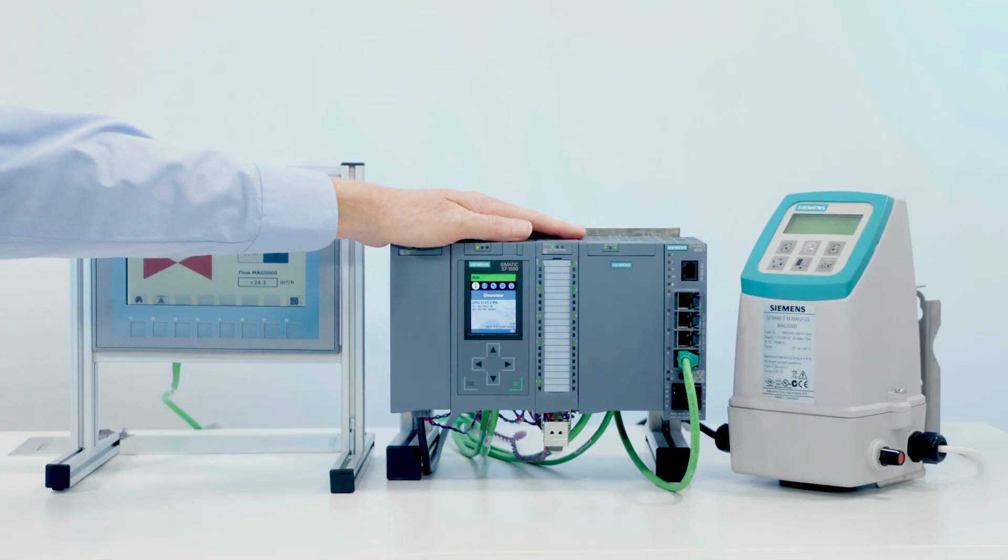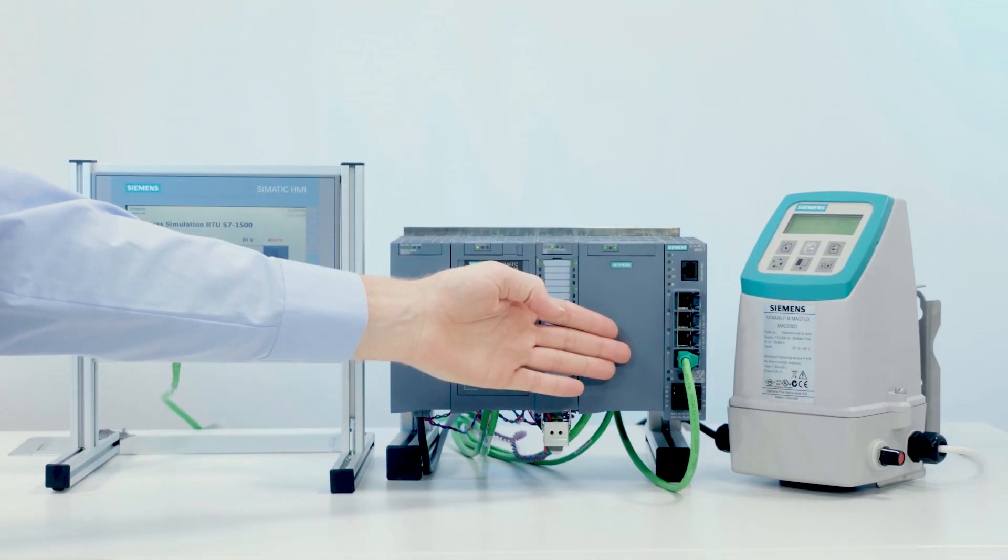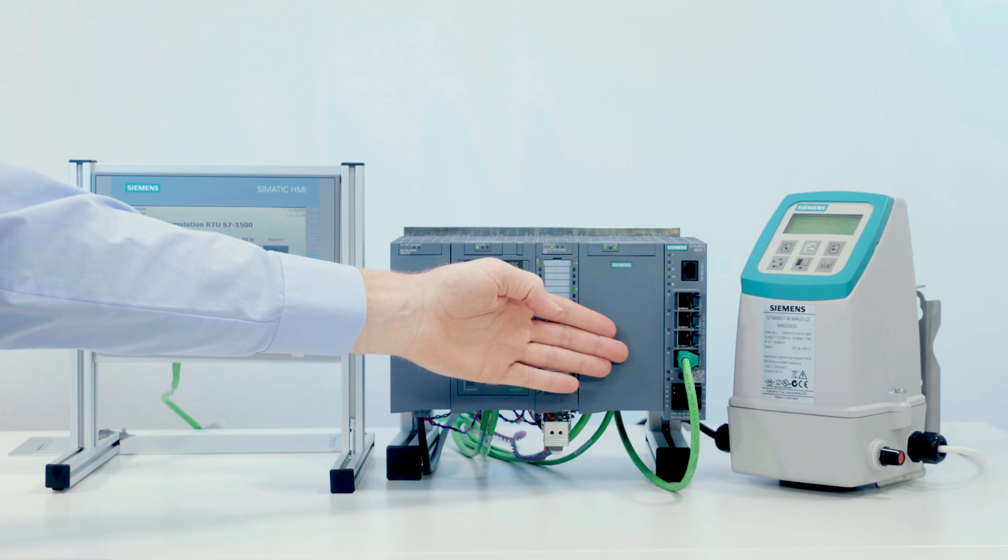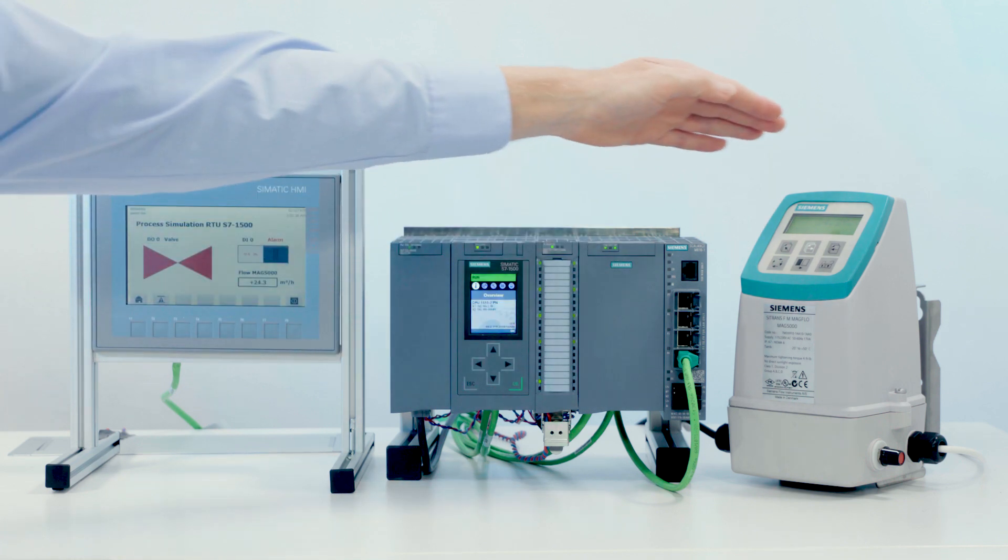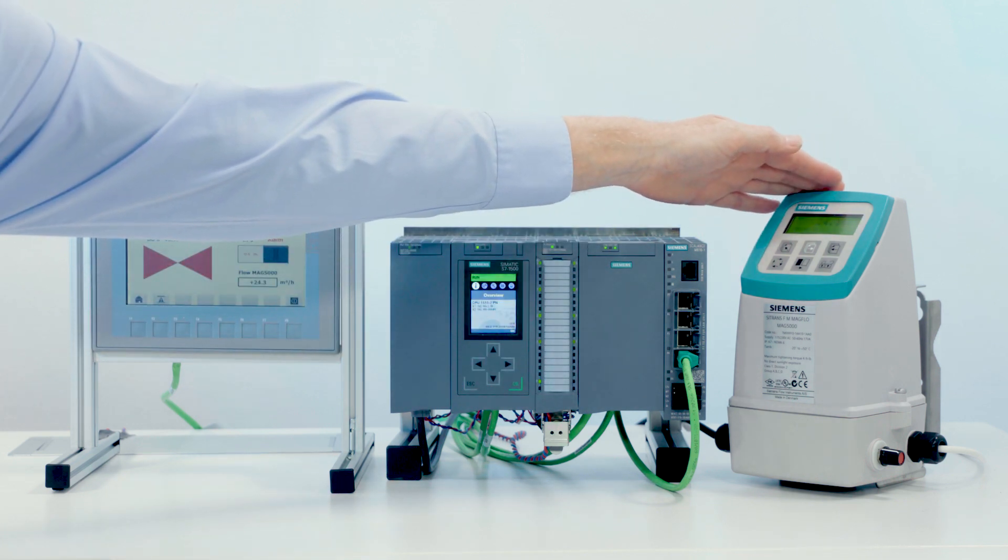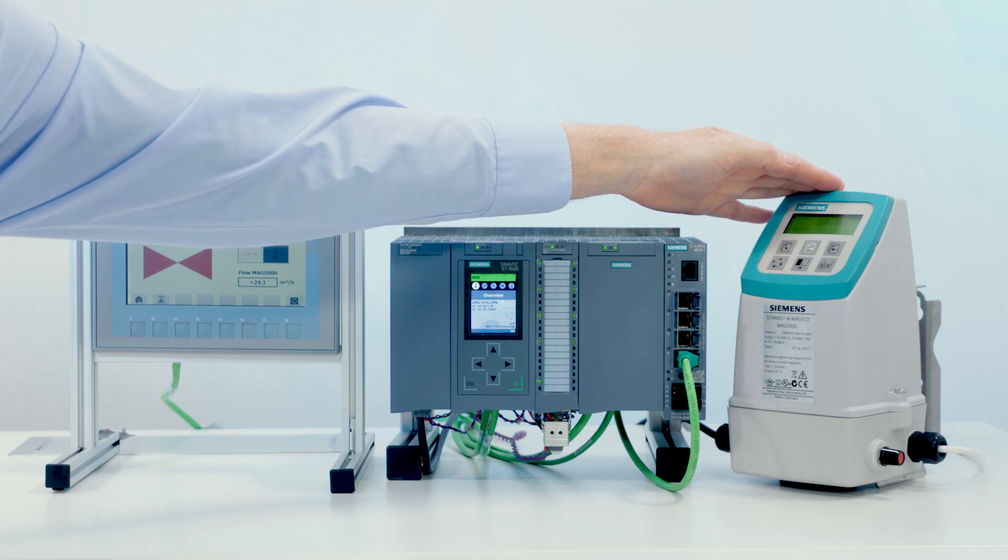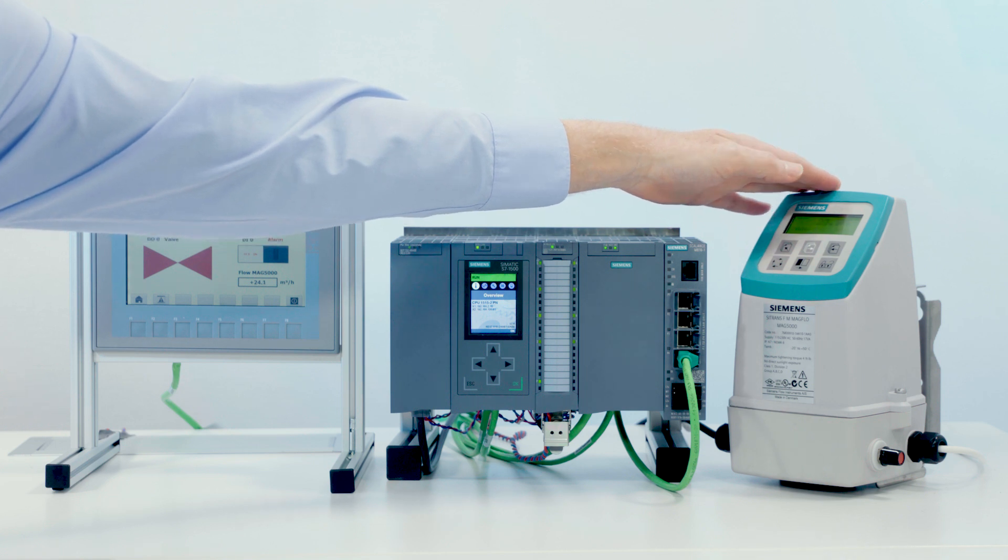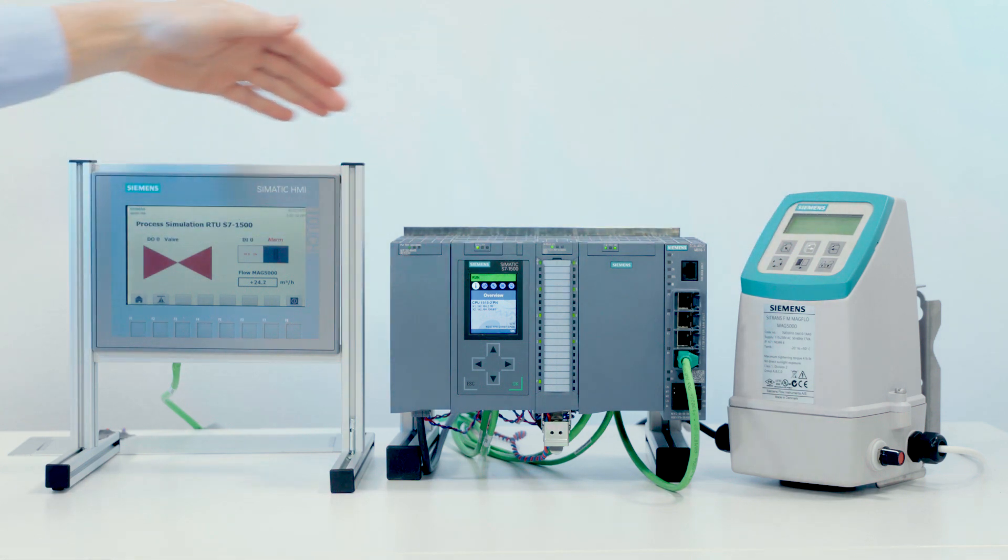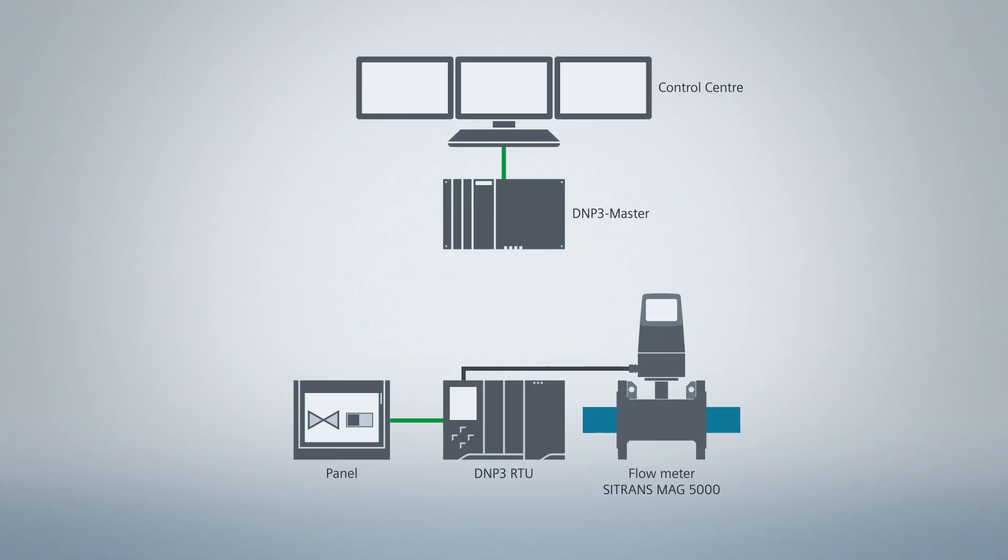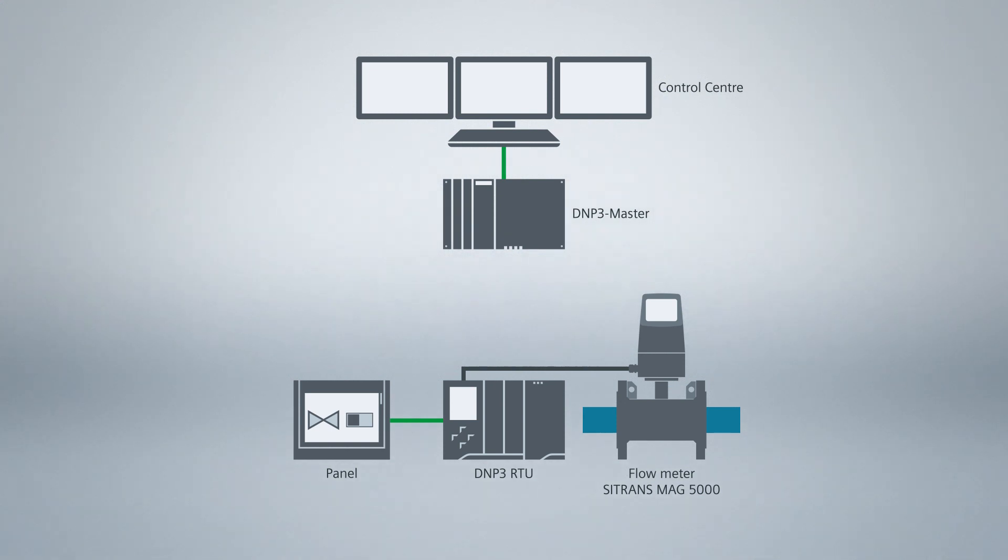Our RTU consists of a SIMATIC S7-1500 and a TIM-1531IRC. The SIMATIC acquires an analog value as a measured value from the connected flow meter SITRANS MAG5000. In addition, it controls a valve. This is simulated here on the panel. The TIM is connected to the PROFINET interface of the SIMATIC with a patch cable in order to read the process values from there.